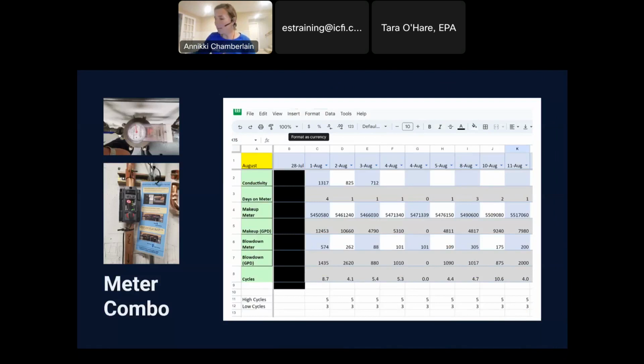Okay, now my favorite, cooling. So this is an example where we have a meter combo. There was an existing meter, they had a makeup meter, but they didn't have a blowdown meter. So again, be very careful with what meters you use on blowdown. I always use ultrasonics, so the clamp-ons are great.